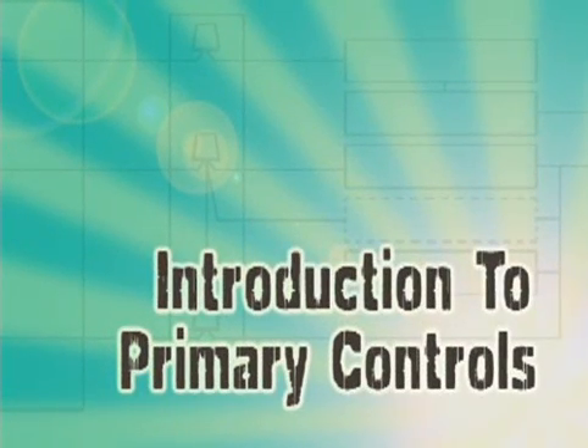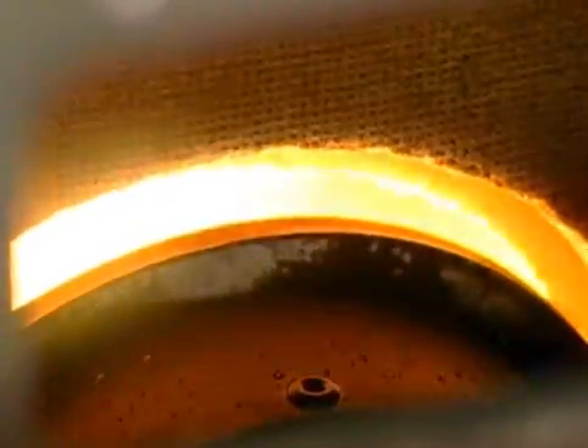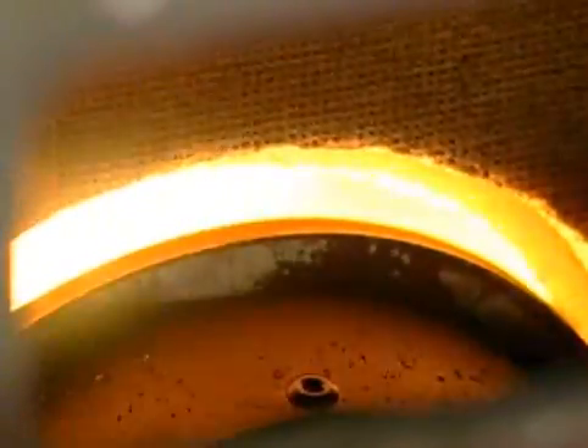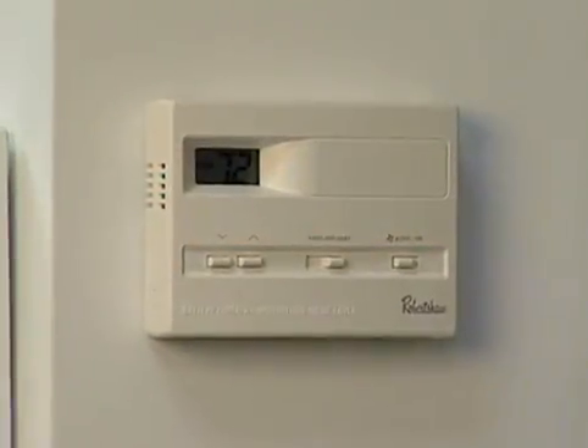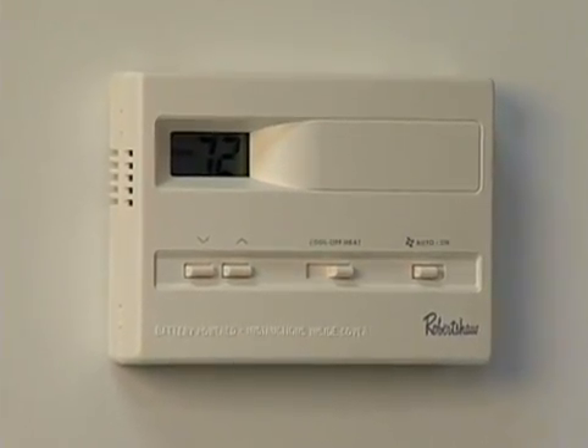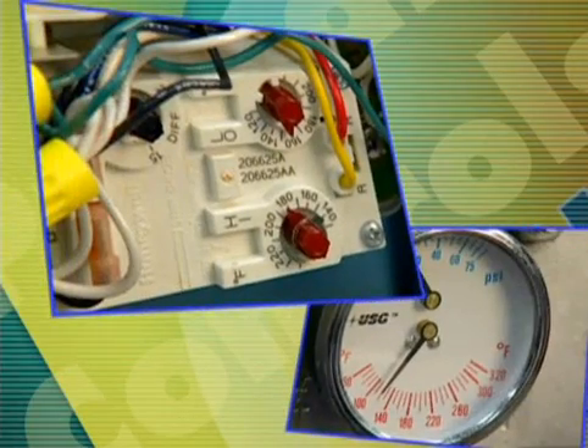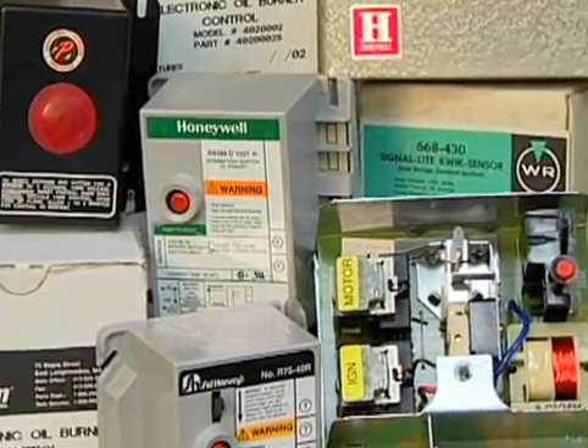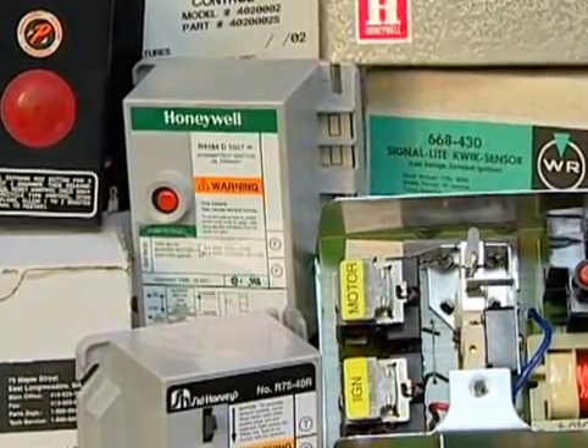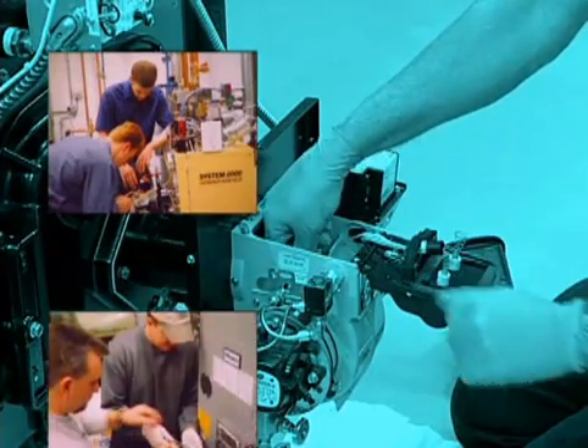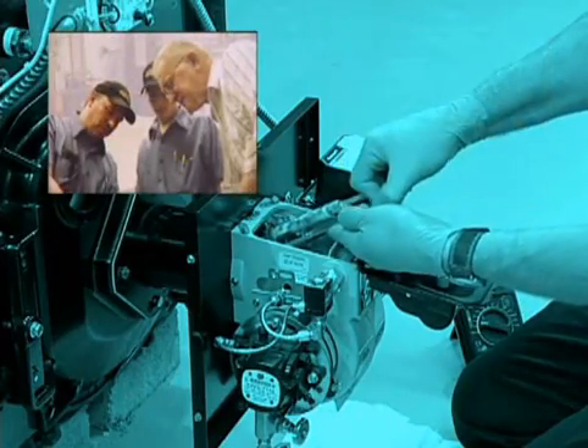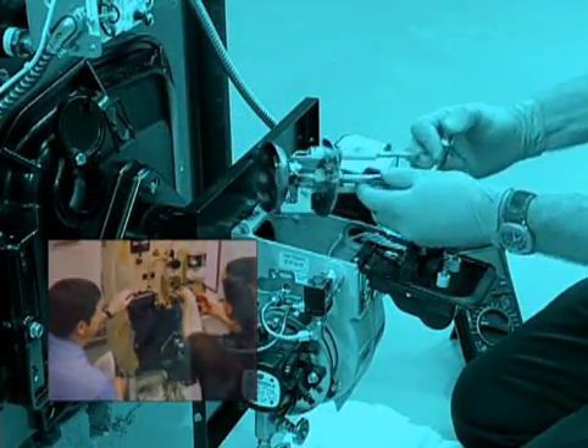Now we'll introduce you to primary controls. The safe, automatic operation of the combustion function of an oil heat system is dependent on the interaction between the thermostat, which opens and closes a circuit based on temperature changes in the heated space, the limit control, which opens and closes a circuit based on temperature or pressure changes in the system, and the primary control, which regulates the operation of the oil burner. In a properly designed, installed, and serviced system, these 3 components work together to safely satisfy a call for space heating, cooling, or water heating.